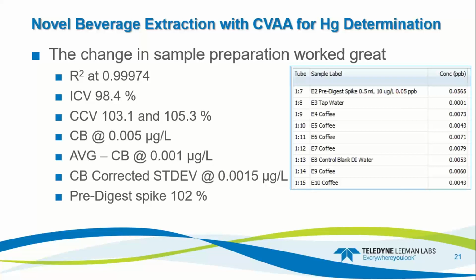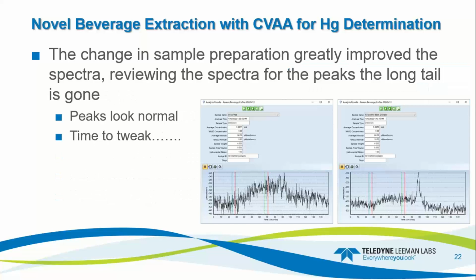Control blank corrected standard deviation at 0.0015 micrograms per liter. Pre-digest spikes came in at 102%. So the change in sample preparation improved the spectra. When reviewing the peaks, the long tail is gone. So here's the sample peak, it's gone. It comes back down to normal. And then here's the blank correct, or the control blank, so it all looks good again.